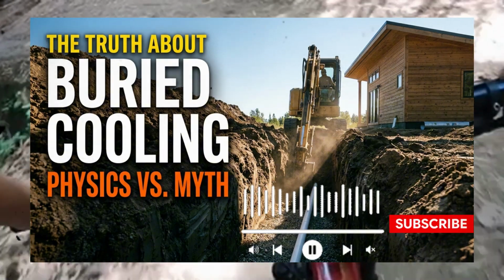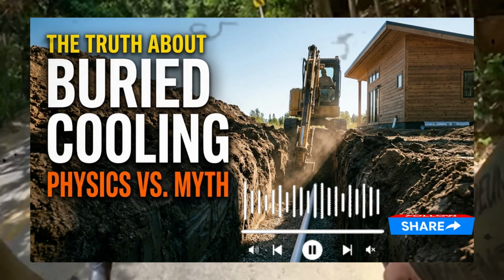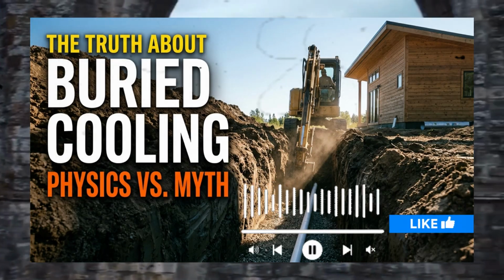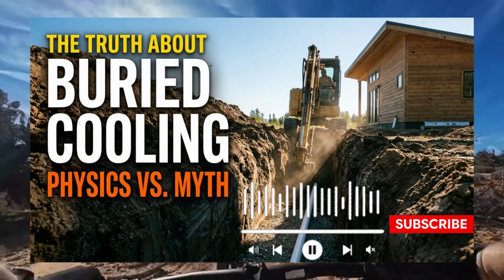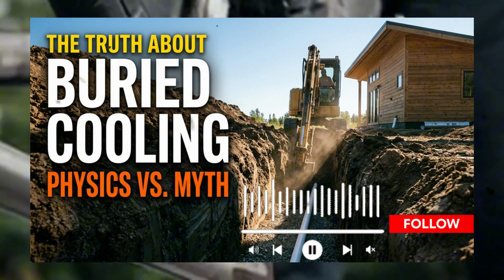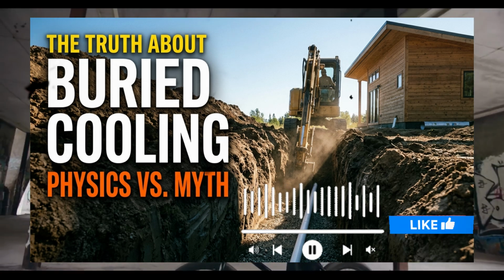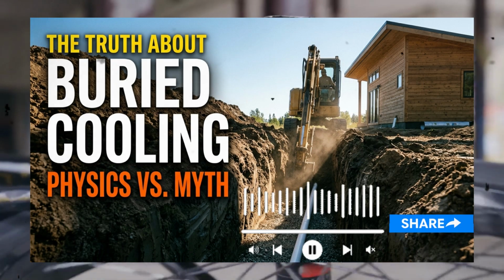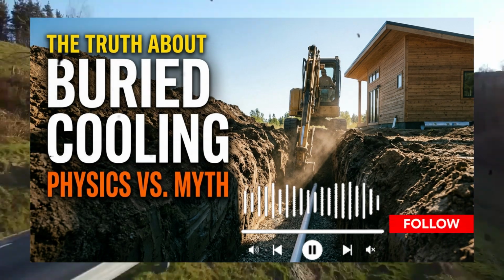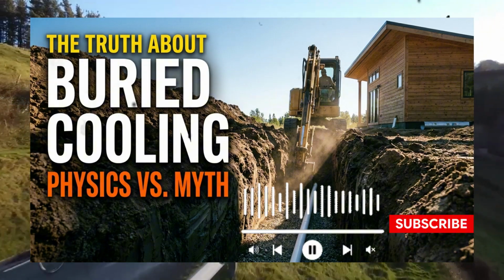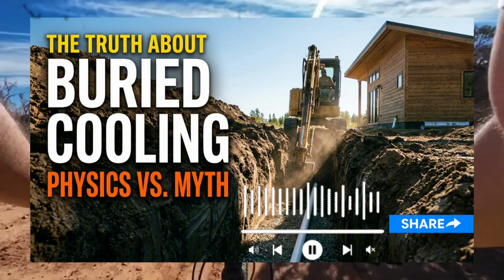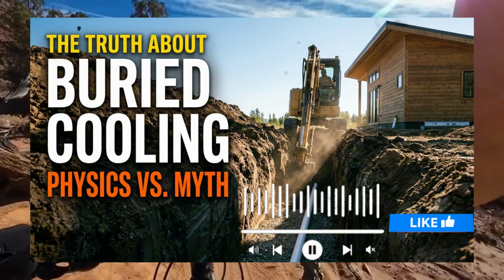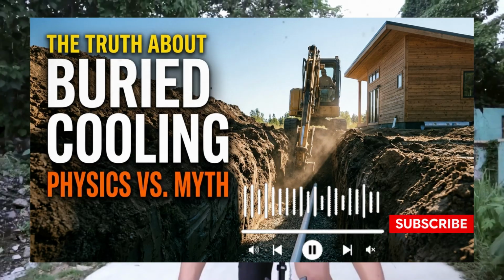This boundary layer acts as a buffer. If you move your air through the pipe too quickly, say, at a high velocity of more than 1,000 feet per minute, the air molecules in the center of the stream rush through the pipe too quickly to ever touch this boundary layer or transfer their heat. They exit the pipe almost as hot as they entered, completely bypassing the cooling capacity of the Earth.